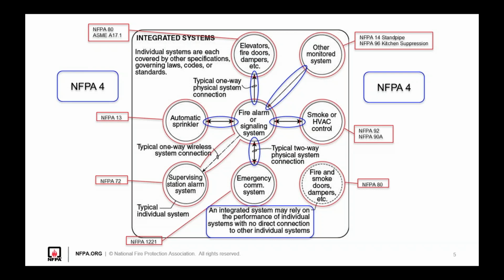One common misconception that we get when talking to people about integrated systems is that integrated systems contain only physical connections, but in reality, integrated systems do not need to be physically interconnected. So, for example, a pressurized stairwell is going to rely on active systems such as the fan, the ductwork, and the louvers. But the system's also going to depend on a passive system that includes the shaft wall construction and the doors and dampers that are used to close off the stairwell and maintain the integrity of the space. So if you had a failure of either the active system, being the fans, ductwork and louvers, or the passive system, say you had a hole in the shaft wall, you're going to lose pressurization within that system. So those are all considered integrated systems.